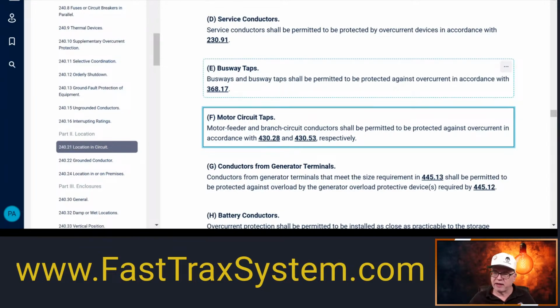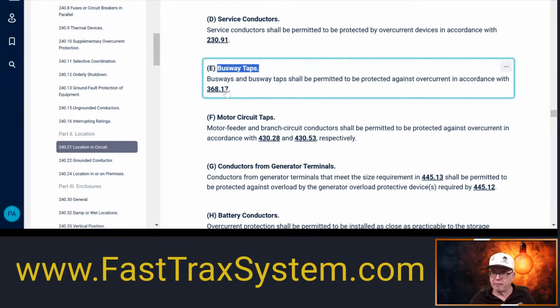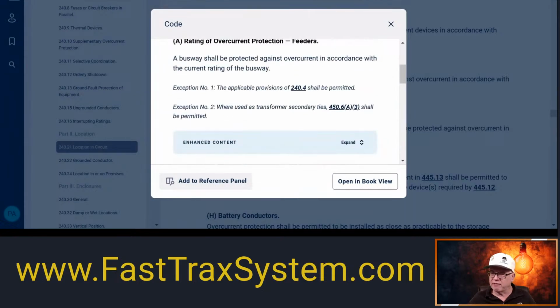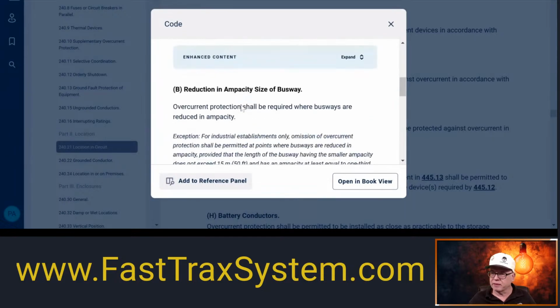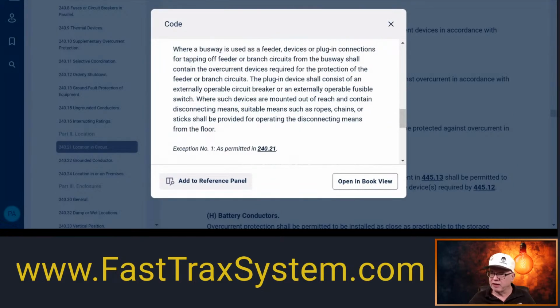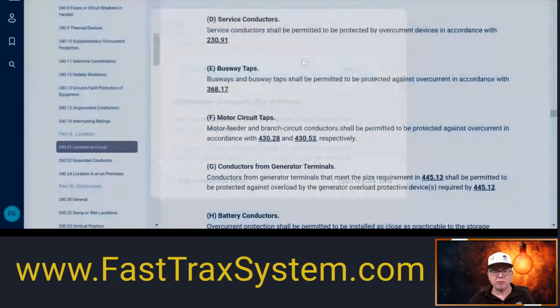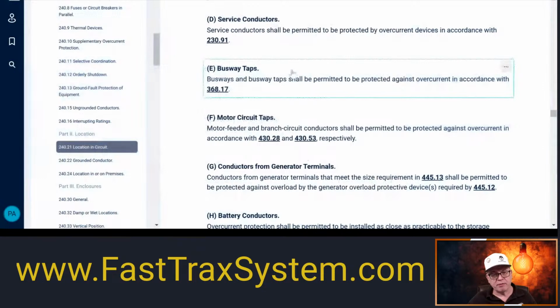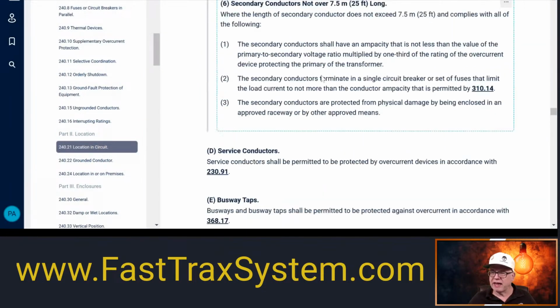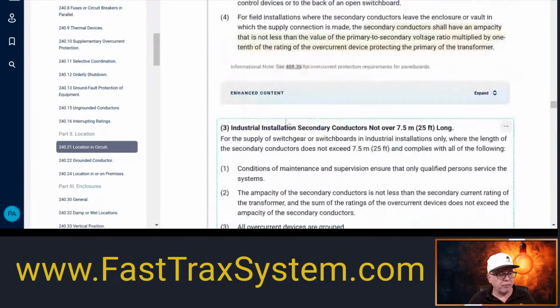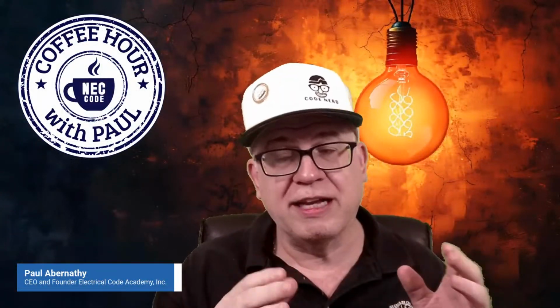And again, here's an example. If you're tapping a busway, it's not going to have overcurrent protection at the tap, so you have rules that you have to follow. And there's the B, and there's feeder and branch circuits. Again, you have rules that you have to follow if you're going to make those types of connections, but that is specifically for a busway type of connection. So all of this has to do with the fact that you're not going to be using overcurrent protection at the point where those taps occur. That's what this is all about.